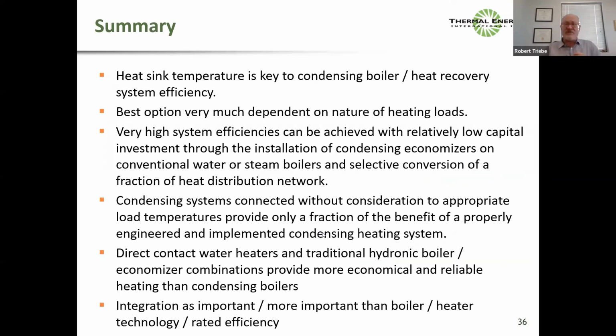Heat sink temperature is key. Condensing boilers don't have efficiencies. Their efficiencies are completely linked to the return temperature of the water and the exhaust temperature of the boiler. Not like a steam boiler. Steam boilers always have the same return temperatures, but it's hypercritical that when you're considering condensing technology, that you look at and optimize your heat sink temperature, sometimes even by retrofitting infrastructure to operate at lower temperatures.